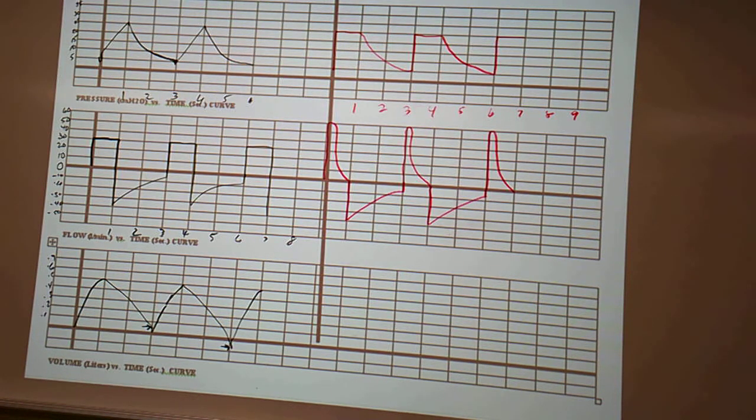Okay, let's explain to grandma how a pressure controlled breath works. When the unit turns on, a high flow rate is exposed to the airways. So I show a real high peak flow. What determines how much flow there is, is the rise time. Higher rise time means I'm going to rise the pressure quicker.